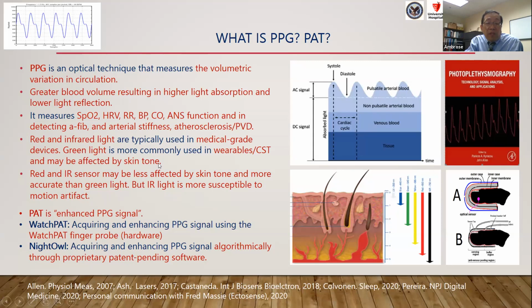And this may be affected by skin tone, and it's important to know that. The red and infrared light sensors are less affected by skin tone and more accurate than green light. But they have more motion artifact.